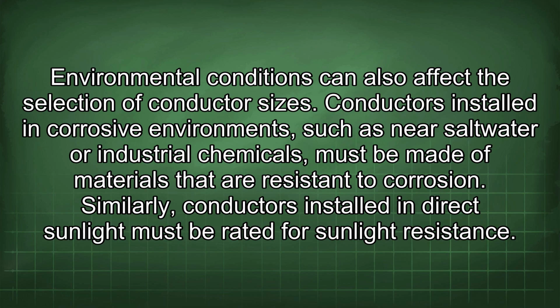Environmental conditions can also affect the selection of conductor sizes. Conductors installed in corrosive environments, such as near saltwater or industrial chemicals, must be made of materials that are resistant to corrosion. Similarly, conductors installed in direct sunlight must be rated for sunlight resistance.